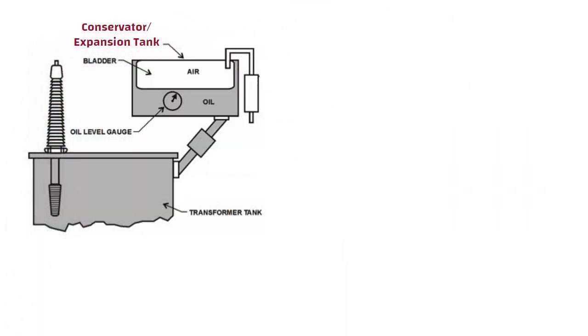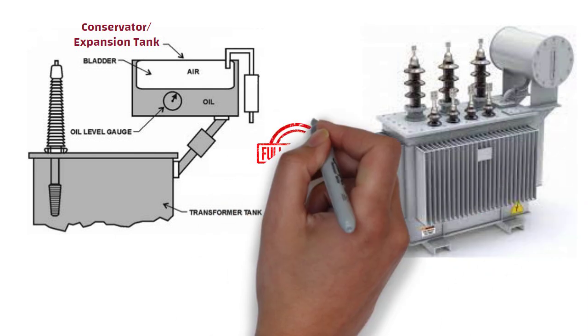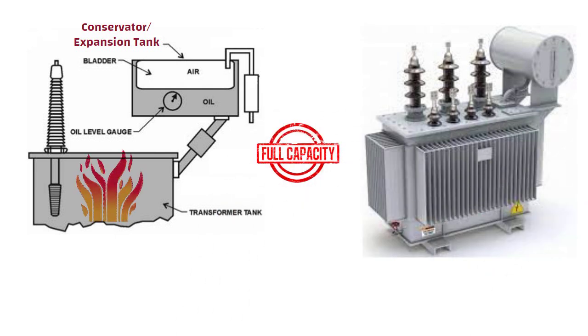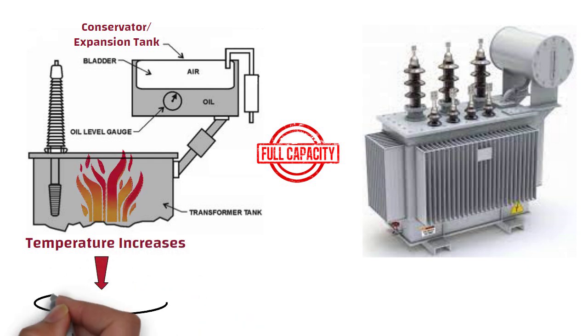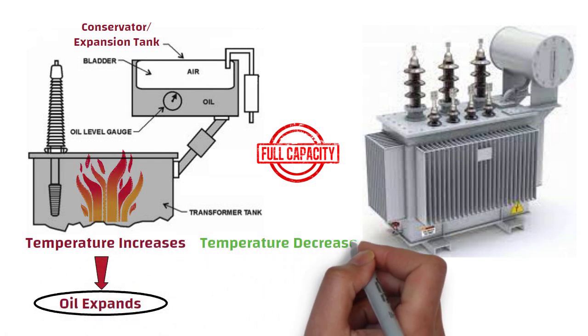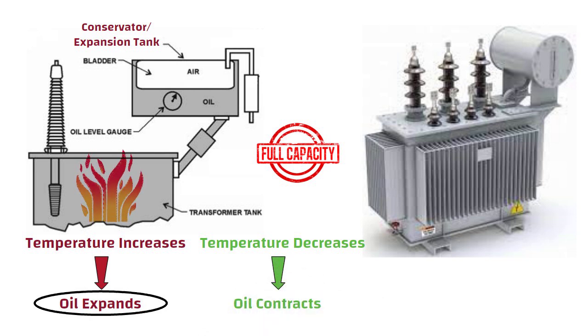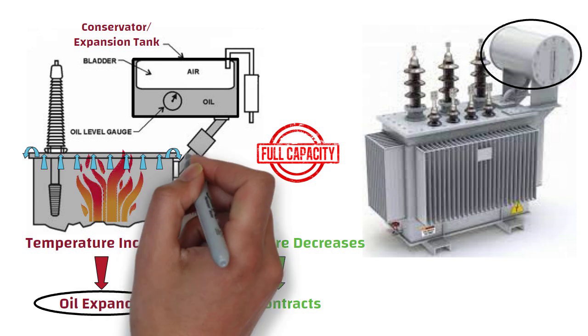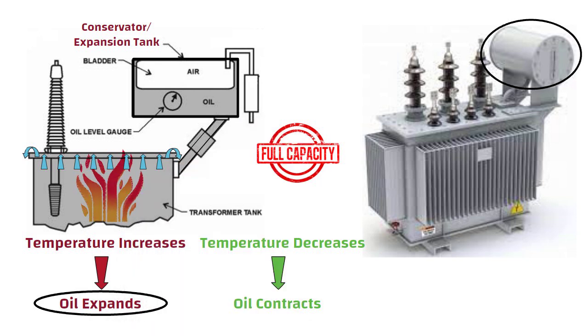Now let us understand the conservator or expansion tank. When the transformer runs at its full capacity or when it overheats, oil alone won't be able to cool the transformer. When temperature increases, oil expands. And when temperature decreases, oil contracts. So when oil expands, it can come out of the tank and start overflowing. To avoid this, a conservator tank is fitted on top of the transformer. It is connected to the main tank through a pipe.